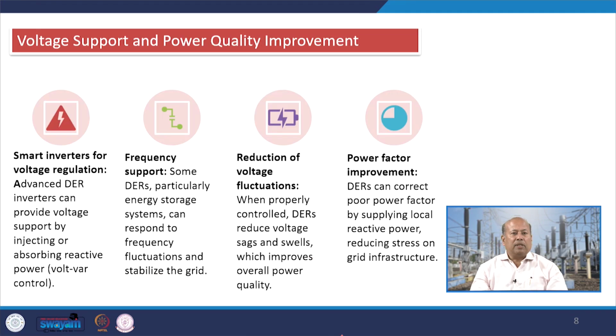Now, what kind of voltage support and power quality improvement takes place? Because we can have smart inverters for voltage regulation, that means advanced distributed energy resources. Inverters can provide voltage support by injecting or absorbing reactive power, that is popularly known as volt var control. It also provides frequency support. Some DERs, particularly energy storage systems, can respond to frequency fluctuations and stabilize the grid.